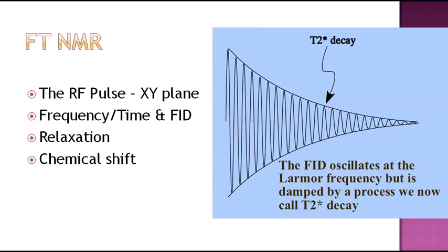At a time, all the protons in the molecule get excited and then relax, and during relaxation it gives a signal which is called a free induction decay. The decay pattern is recorded for each proton, and that decay is converted into a spectrum using the Fourier transform series in mathematics. That's why it is called FT-NMR.